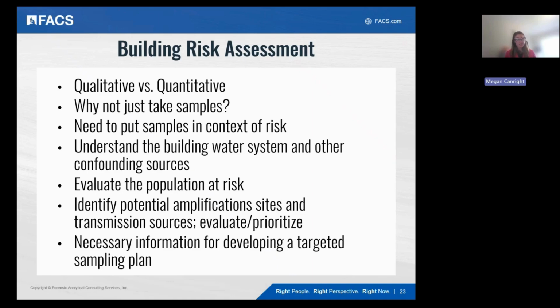And the population of the building needs to be evaluated for risk as well. So the qualitative risk assessment is done to identify potential amplification sites and transmission sources, and then help evaluate and prioritize which of those risks to address first. It's really necessary information for developing a targeted sampling plan. So those samples are taken to validate the qualitative risk assessment results, to confirm that the areas of risk that were identified are actually areas of risk, rather than just taking random samples and having to interpret those outside of the context of the building.